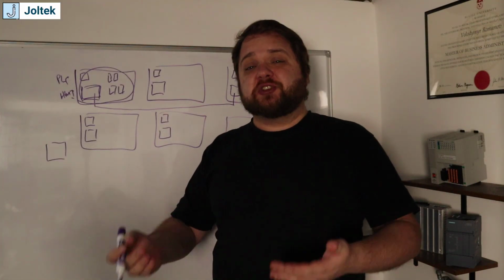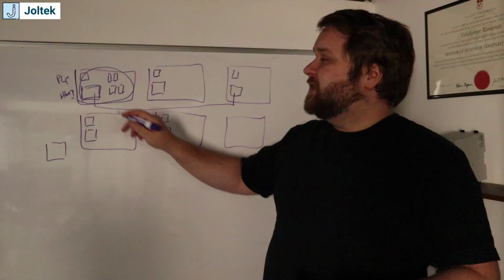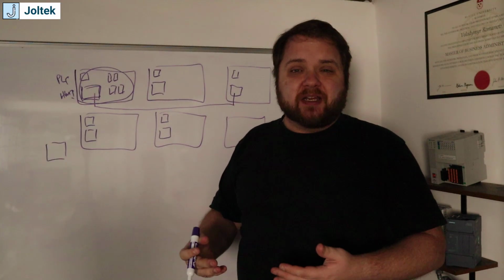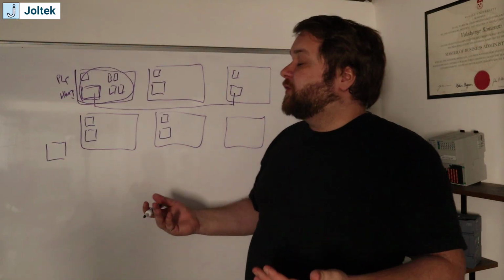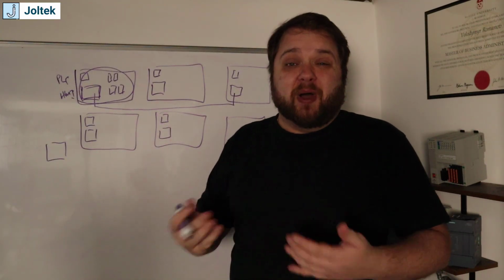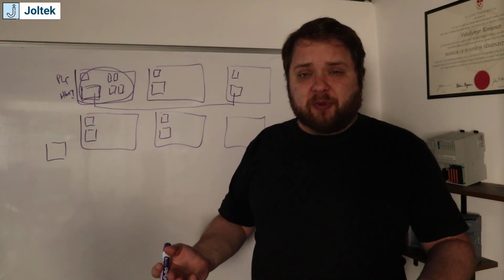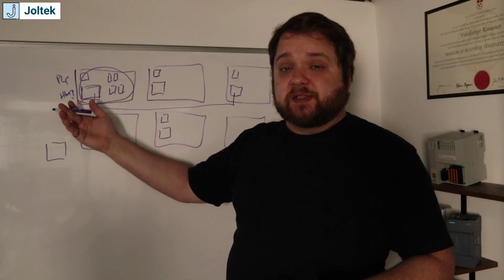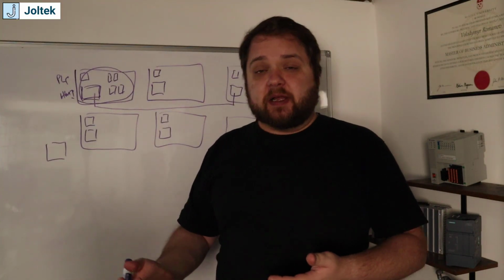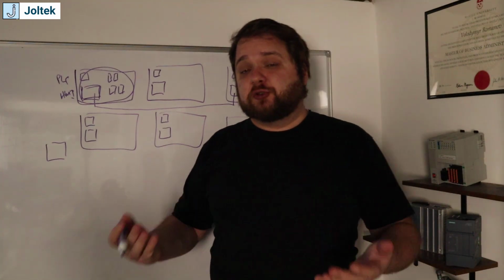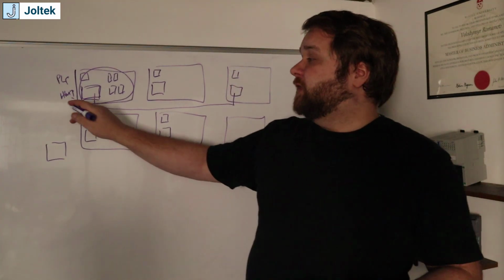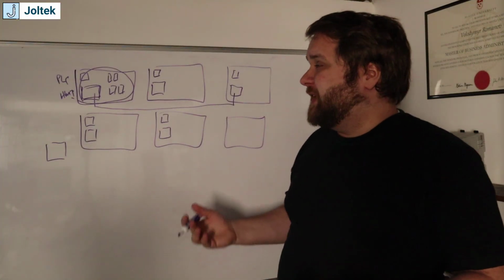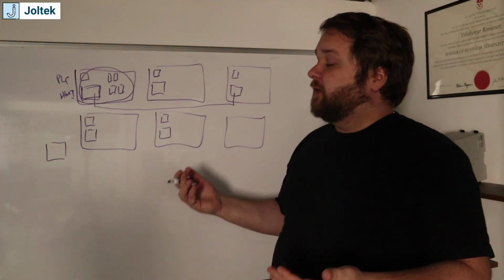That being said, as I mentioned in the previous video, both of these systems aren't going to be databases. They are not meant to back up enormous amounts of data. Of course, it is possible to use a PLC to buffer some of that information for a couple of hours, maybe a couple of days, depending on the stream. The same goes for your HMI systems. It is capable of displaying the data. It is capable of displaying historical information. It is very often capable of storing some of that information on a USB or an SD card, but it is not necessarily a SCADA in and of itself.